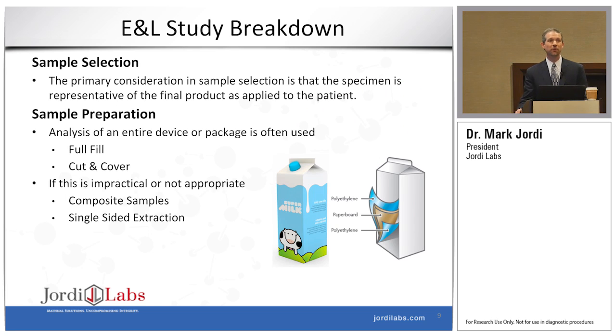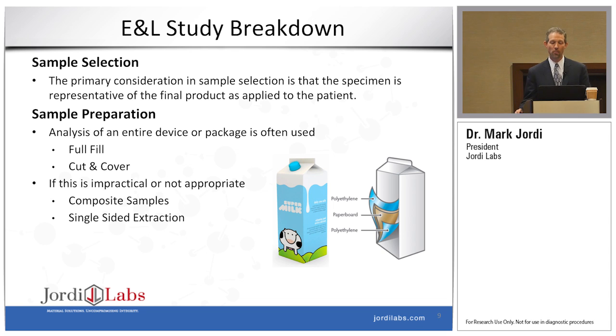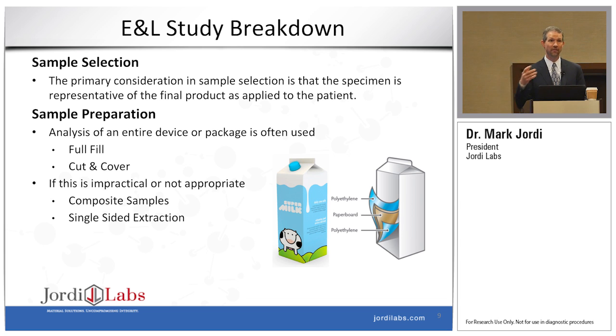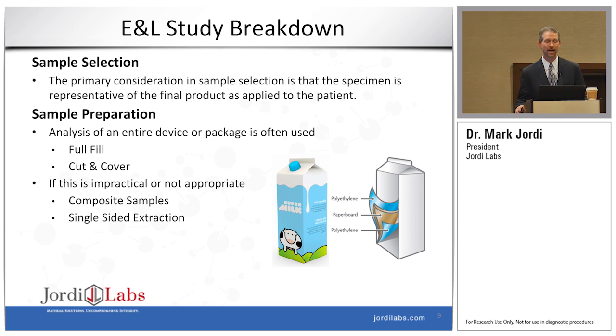When we consider the sample selection process, typically we care most about ensuring that the sample we're going to utilize is exactly like that which will be used in the final use situation. We want to make sure we're using the same production lines and the exact same material supplies, because all of those can affect the extractables and leachables profile.